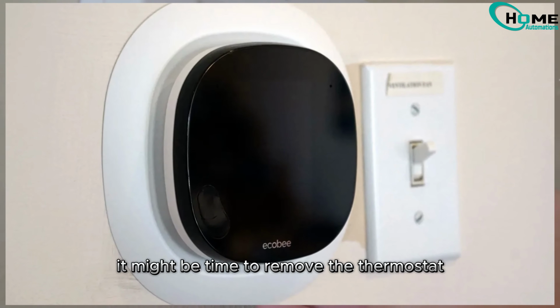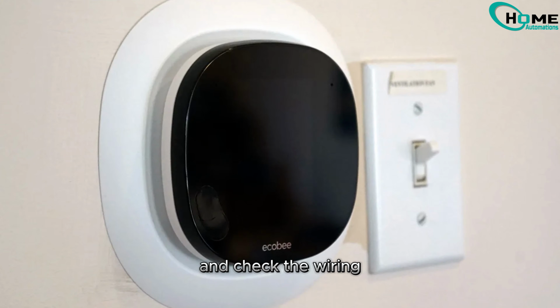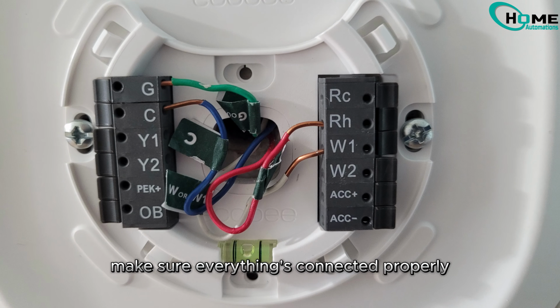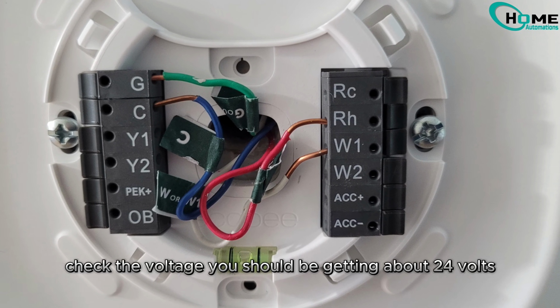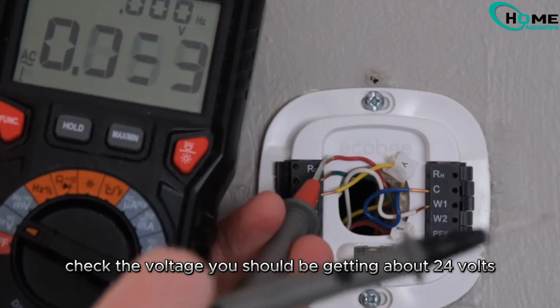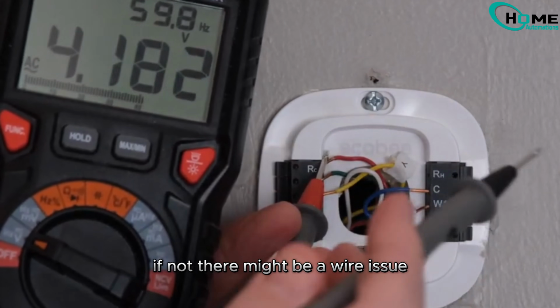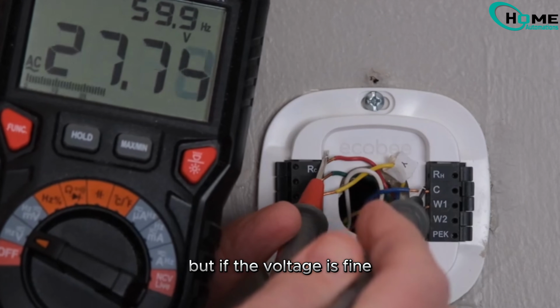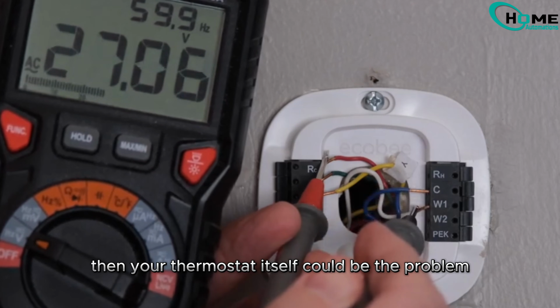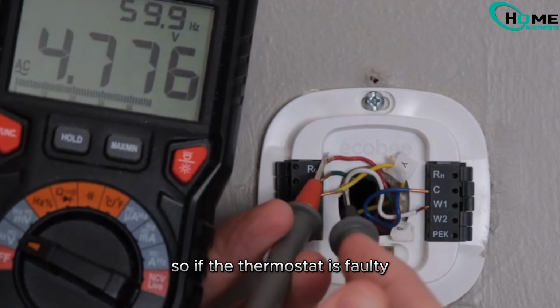Give it some time. If you're still not getting power, it might be time to remove the thermostat and check the wiring. Make sure everything's connected properly. If you've got a multimeter, check the voltage. You should be getting about 24 volts. If not, there might be a wire issue. But if the voltage is fine, then your thermostat itself could be the problem. So, if the thermostat is faulty, you might need to replace it.